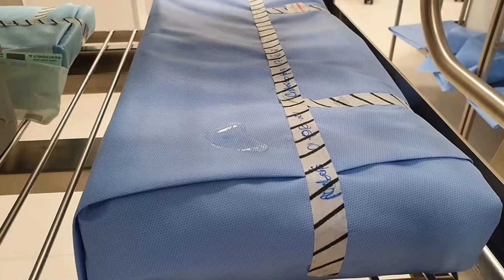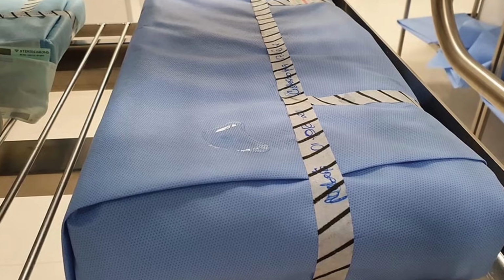A wet load is when something went wrong in the cycle where moisture retained on the packaging leaves the packages wet and dripping moisture once they've been pulled out of the sterilizer. This could happen for many reasons, including sterilizer malfunctions, density of the sterilizer load that exceeded the IFUs, bad quality steam, and another major contributor is not drying instruments before sterilization.